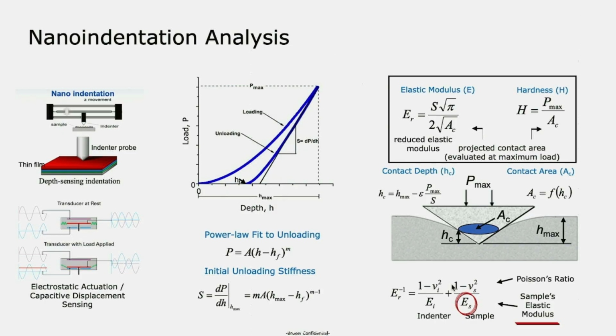If we look at this, our transducer outputs the load and the displacement. Displacement is just representative of the deformation of the material. And then the force is what we give on the tip, right? So this is totally about the mechanical properties response from the material. We can use this curve to apply the mechanical model from Oliver and Pharr, which was developed in 1992. Then we can calculate the elastic modulus and the hardness here.